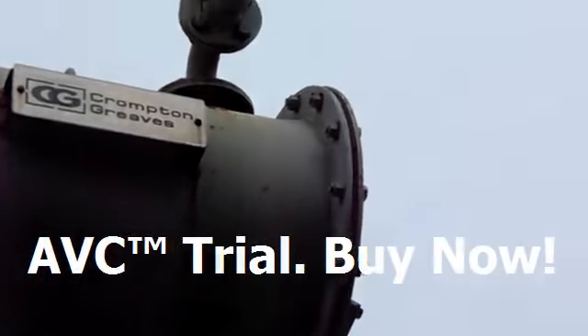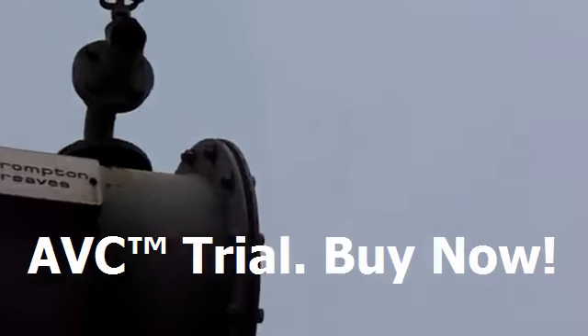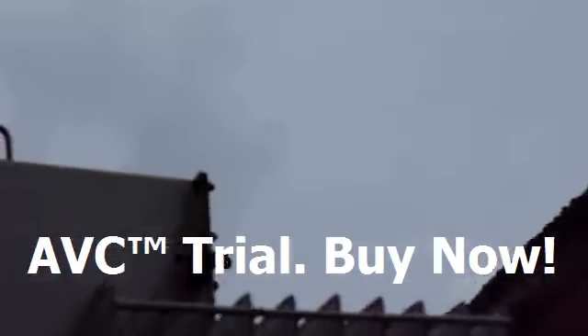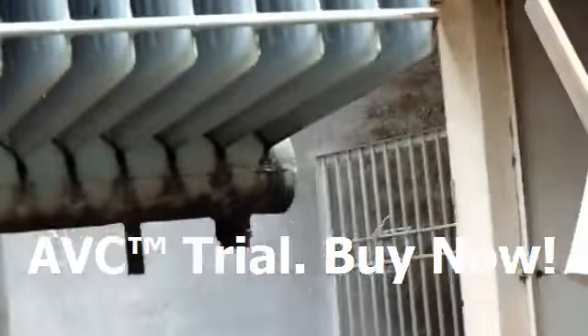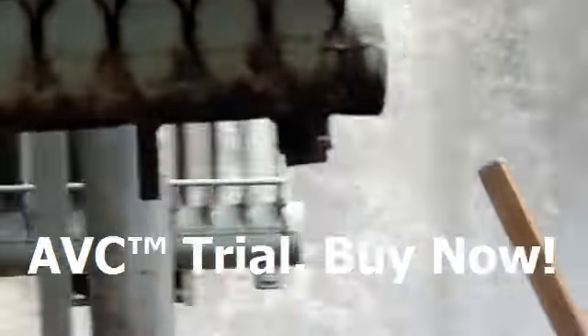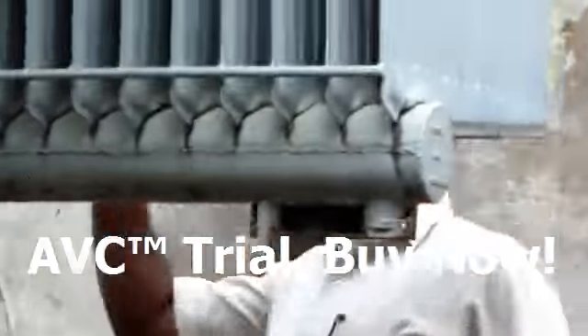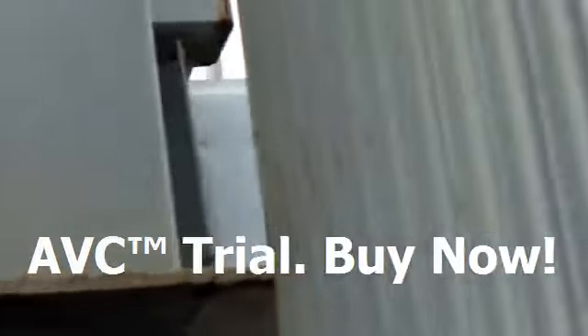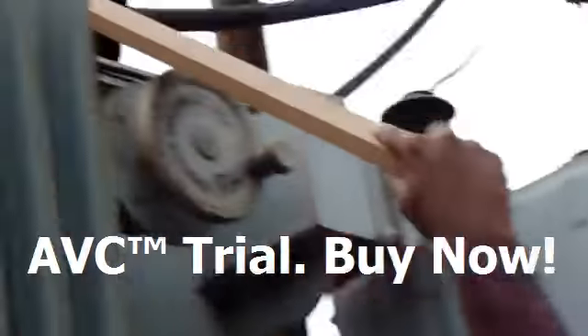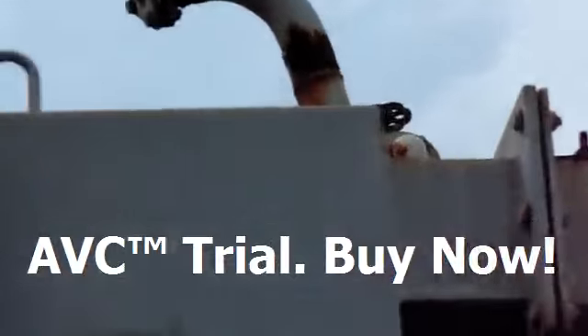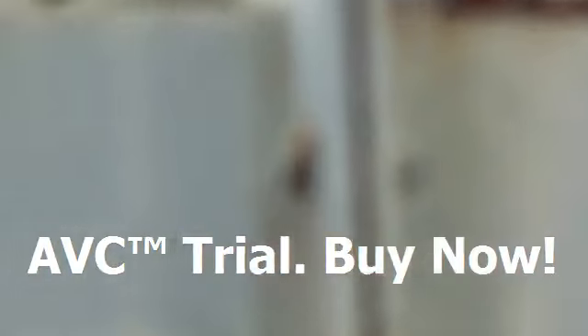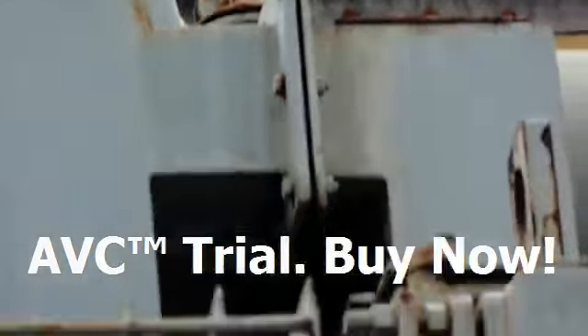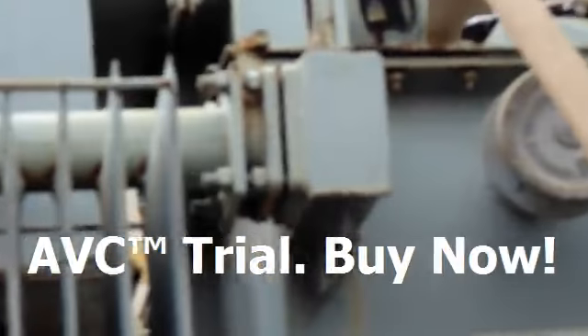Then there is another important thing you have to see, that is the temperature gauge. You have got a temperature gauge where you can see the temperature of the oil. This is the temperature gauge, and you can see it is connected here, where you can see the temperature of the oil. The temperature of the oil should never exceed 90 degrees centigrade. So you can see there is a temperature gauge provided.